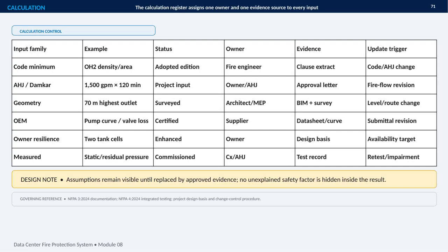This slide shows how the calculation register controls the basis of design. The central principle is every input has one owner and one evidence source. That makes the calculation traceable, and it also makes changes easier to manage. The register groups inputs into 6 families. Code minimums, such as the OH2 density and area, are owned by the fire engineer and supported by a clause extract. AHJ or Damkar requirements, including the 1,500 gallon per minute flow for 120 minutes, are confirmed through the approval letter.